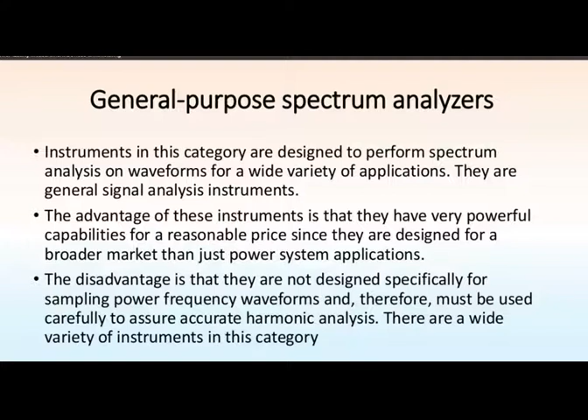The disadvantage is that they are not designed specially for sampling power frequency waveforms and therefore must be used carefully to assure accurate harmonic analysis. There is a wide variety of instruments in this category. So this is the basic disadvantage of the general purpose spectrum analyzer.